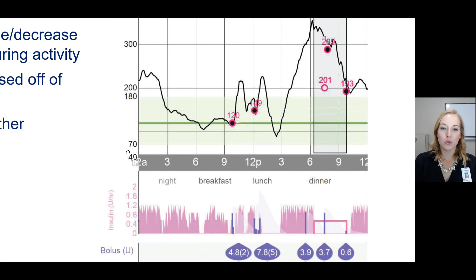In auto mode, you do have to be meeting criteria to remain in auto mode. Some of the criteria are having calibrated your sensor recently. You have to have been using a certain amount of basal consistently. If your pump has been suspended for too long, it gets nervous that it's going to harm you, essentially, and so it exits out of auto mode and resumes your background basal rate. Additionally, if you're running high for too long, it will exit out because it wants to safeguard against too much extra insulin being given in case there is a sensor error.